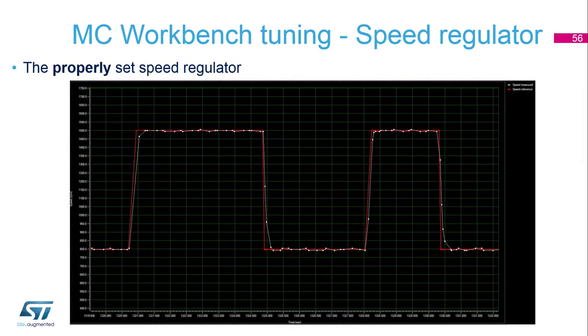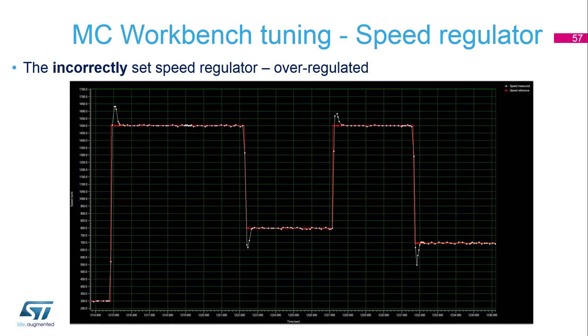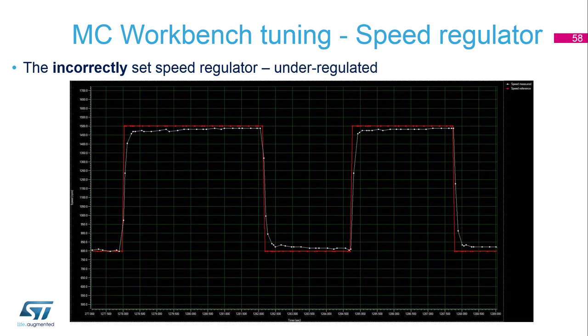This is the setup of a properly set speed regulator. However, if you see artifacts with overshoot and undershoot, this means the regulator is over-regulated — in that case, decrease the KI parameter. If you see under-regulation with no fast reaction and limiting over a long time, you need to increase the KI parameter.